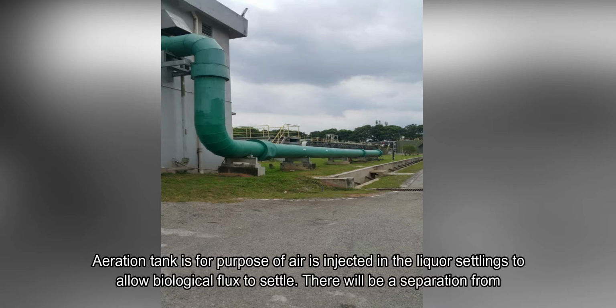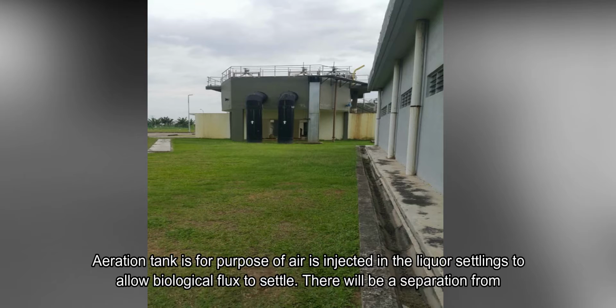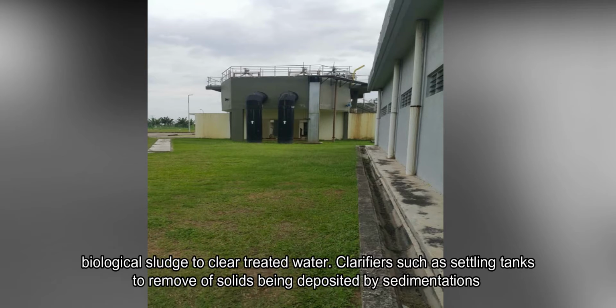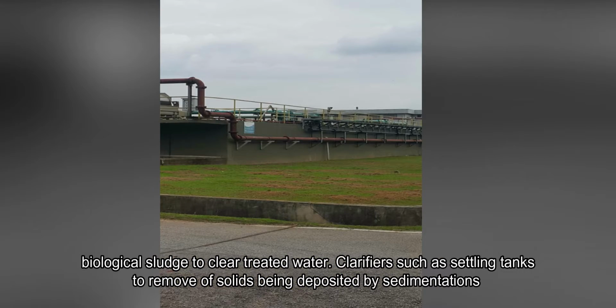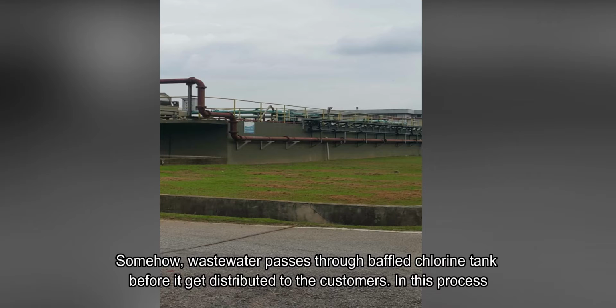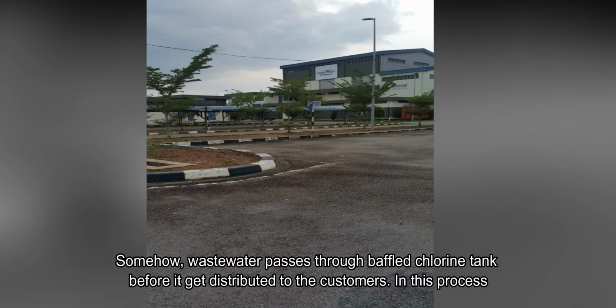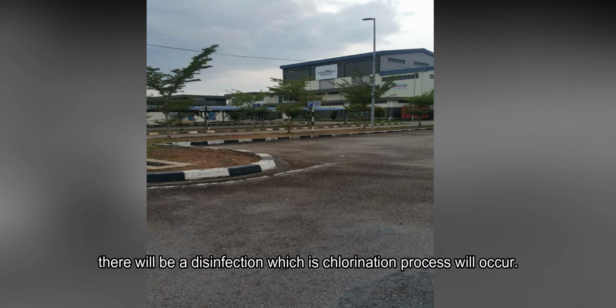In the aeration tank, air is injected into the liquor to allow the biological floc to settle. There will be a separation of biological sludge from clear treated water. Clarifiers, such as settling tanks, remove the solids deposited by sedimentation. Then the wastewater passes through a baffled chlorine tank before it gets distributed to customers. In this process, disinfection, which is the chlorination process, will occur.